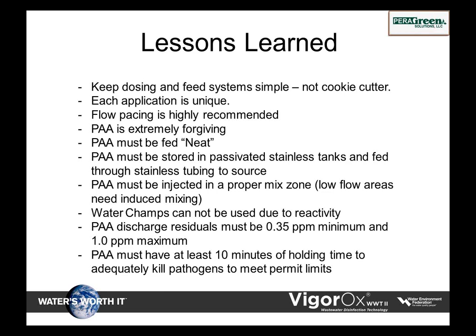You can't feed it in low flow areas. It will not mix. You've got to have some type of turbulation, overflow weirs, agitation, but do not use water champs. The alloys used on the water champs are not compatible. Titanium is not compatible with PAA, and you don't need that much mixing. It's very close to the density of water. It will fully be miscible. The key is you just want it in there as fast as you can at that high dosage, and that's where you're getting the kill. Also, again, bottom floor, 0.35 parts per million and 1 part per million max.